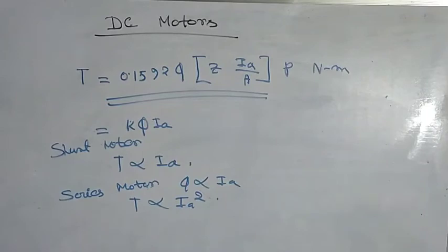Also it can be seen that for a particular armature current, the torque is independent of the supply voltage, which is not true in case of a shunt motor. From this it is clear that even though a shunt motor is operated under constant voltage condition, when a large torque is required, the current input to a series motor is smaller than for a shunt motor.